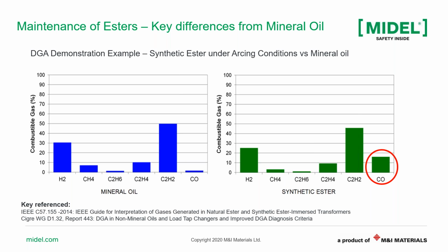Now this is a test conducted under arcing conditions. On each of these charts, you can see on the x-axis the key gases: hydrogen, methane, ethane, ethylene, acetylene, and carbon monoxide. And on the y-axis, you see the combustible gases percentage within that test. So you can see mineral oil is almost the same pattern of gases as that of a synthetic ester, with two observed differences. One is that synthetic ester can have more carbon monoxide compared to mineral oil, and the other is that the volume of gases produced in synthetic ester from a fault is slightly lower than that produced in mineral oil.